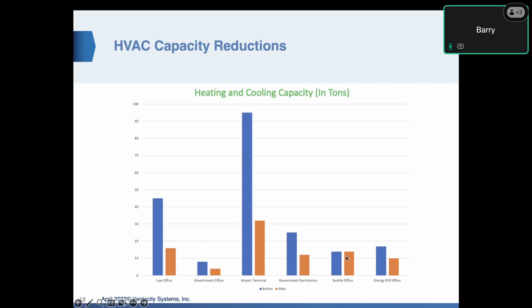This is the exception. It was really a matter of somebody donating them two 6-ton heat pumps. We're still at over 80% HVAC energy savings on that project, but they took 12 tons of rooftops off and replaced it with 12 tons. That's kind of an exception. And fortunately, the heat pumps can cycle at very variable load, and we're able to manage it no problem.